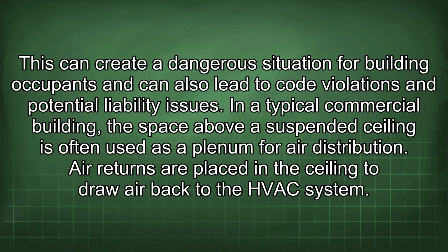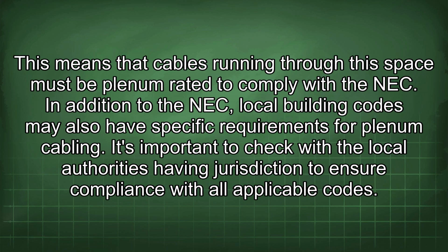In a typical commercial building, the space above a suspended ceiling is often used as a plenum for air distribution. Air returns are placed in the ceiling to draw air back to the HVAC system. This means that cables running through this space must be plenum-rated to comply with the NEC. In addition to the NEC, local building codes may also have specific requirements for plenum cabling. It's important to check with the local authorities having jurisdiction to ensure compliance with all applicable codes.